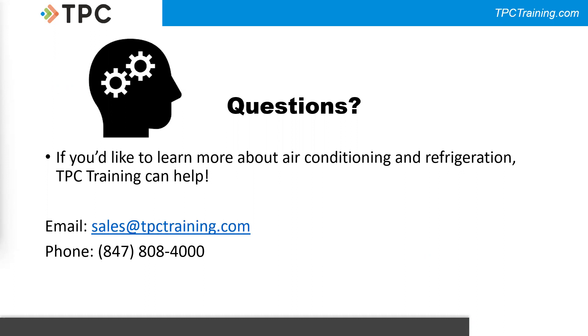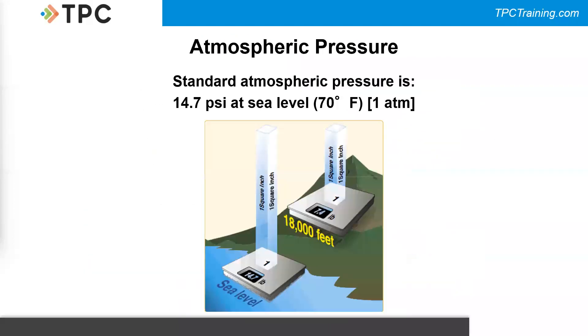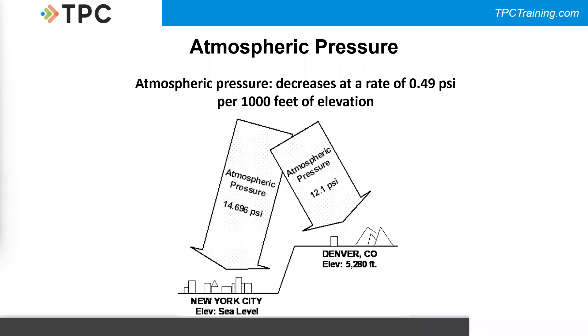A question from Antoine about elevation: if you're in Denver, would your zero point be at 12.1 PSI? Exactly — in Denver, zero PSIG corresponds to 12.1 PSIA, whereas in New York City zero PSIG corresponds to 14.696 PSIA, now rounded to 14.7. If you take your gauges from one location to another it's important to recalibrate them; otherwise you won't get an accurate reading. Newer digital gauges have a button for automatic calibration.